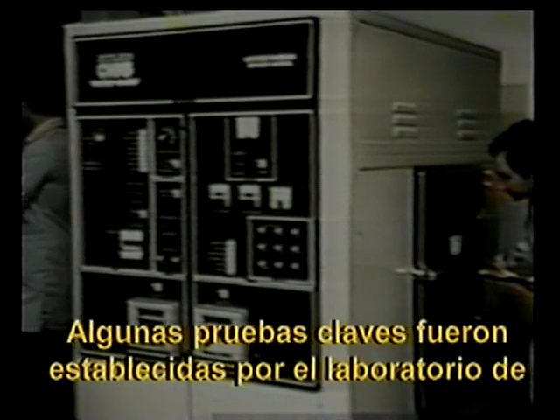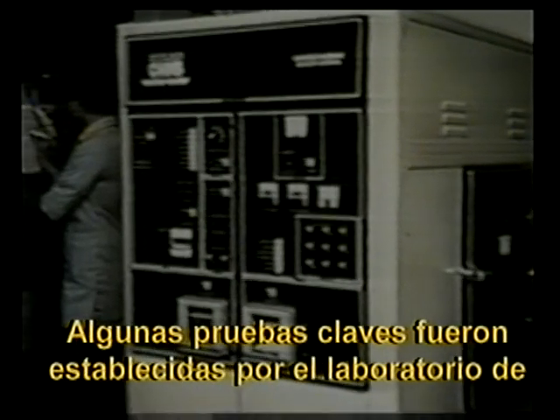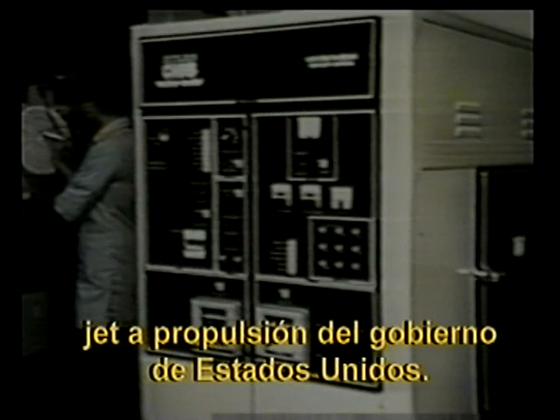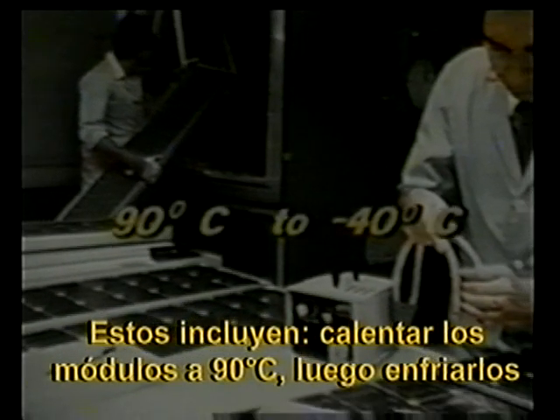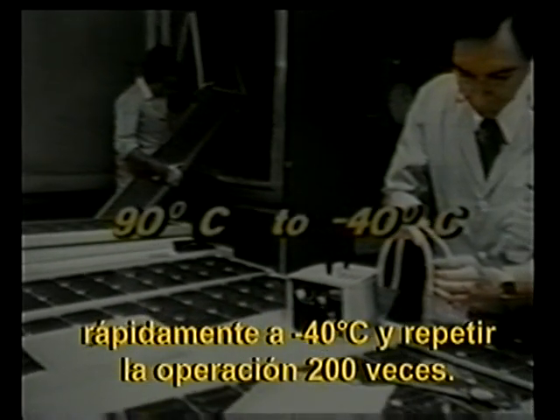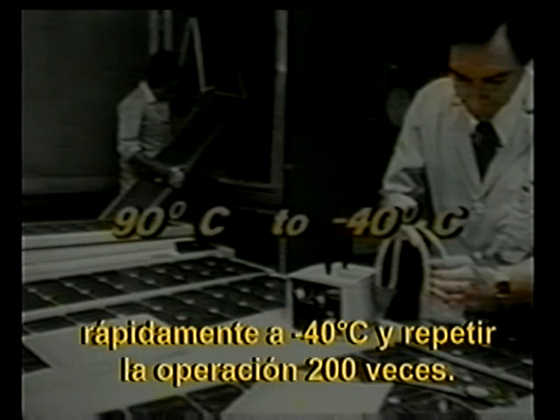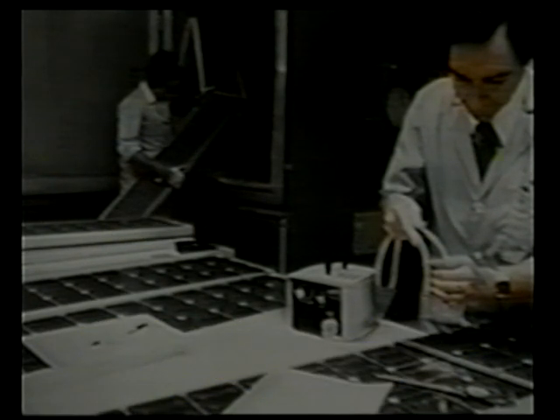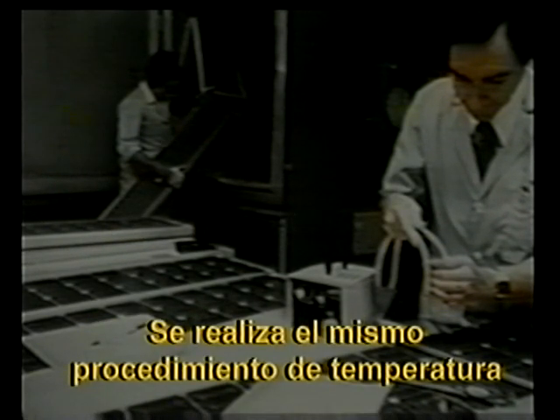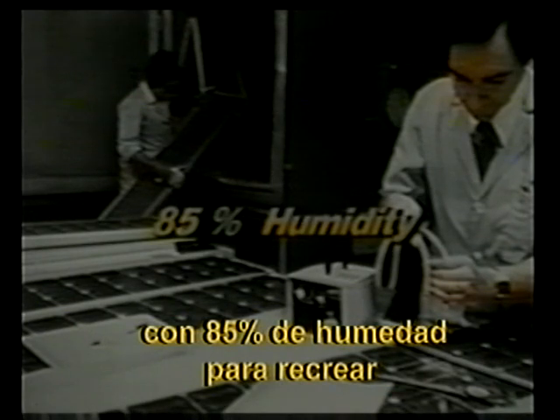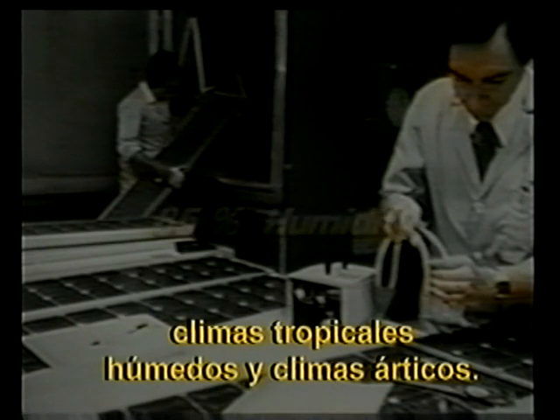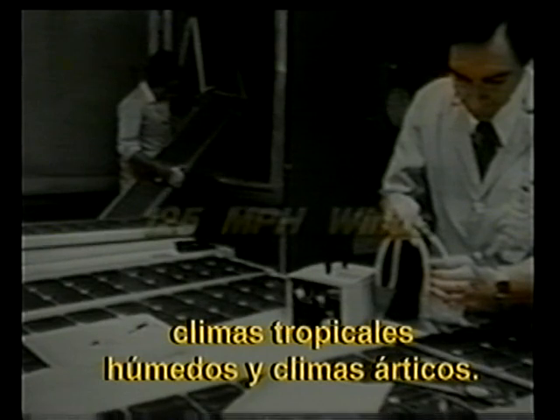All module designs go through elaborate environmental tests. Some key tests have been established by the Jet Propulsion Laboratory for the U.S. government. They include heating modules to 90 degrees Celsius, then quickly cooling them to minus 40 degrees Celsius, and doing this 200 times. Doing the same temperature cycling in 85% humidity to recreate humid tropical and frozen Arctic climates.